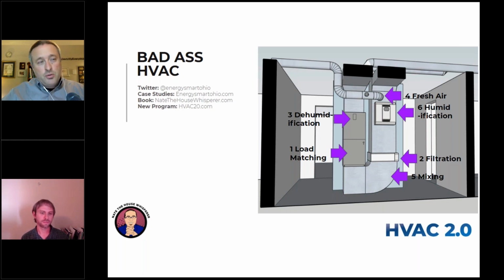That'd be fine too, although you need to know what happens if it fails. The other curse is if that's running but the air handler isn't, you can be blowing — classic one. I've had two issues with ERVs causing comfort problems, and that was an ERV, not just a fresh air intake. Both times it was like 5 degrees outside, so they're kicking out 45 to 50 degree air — noticeably cold, not freezing, but nobody wants to sit there. So if the air handler isn't running continuously and you're pushing 50 or 100 CFM into the ductwork, and it's finding its way wherever it can, you're probably going to get a comfort complaint. Which is why we just say: let's run the air handler and get most of what we need.